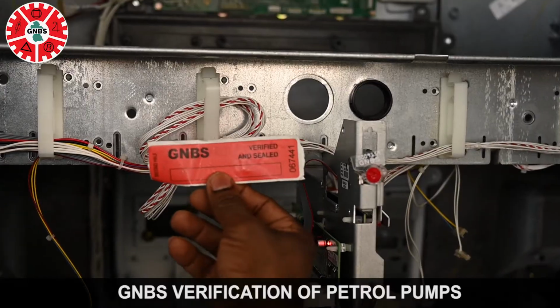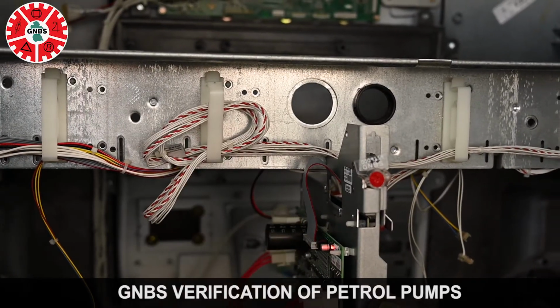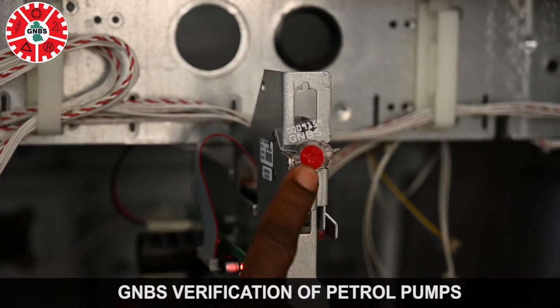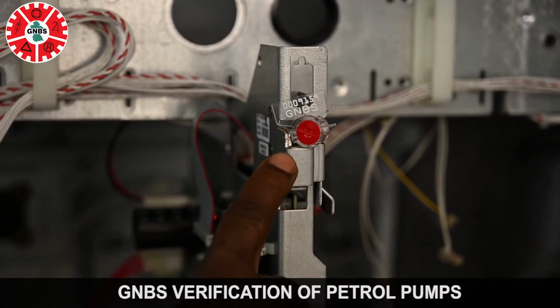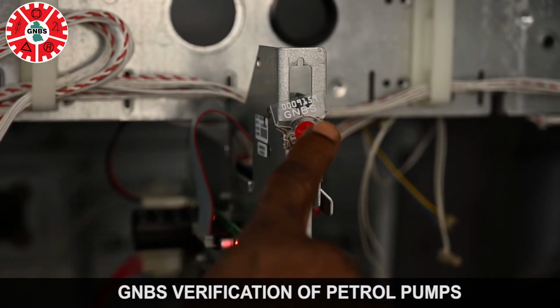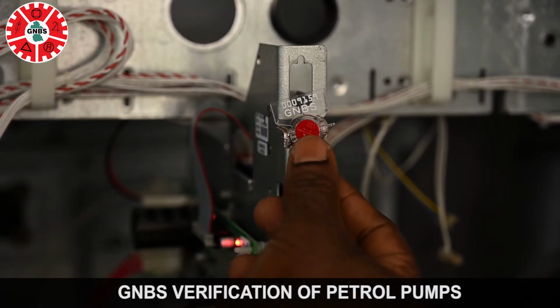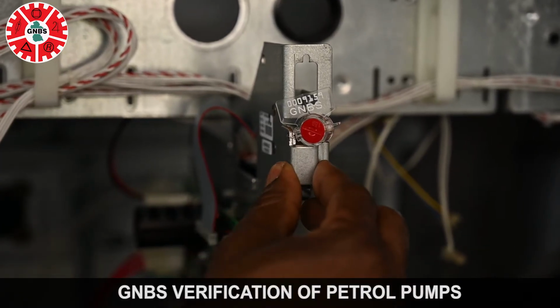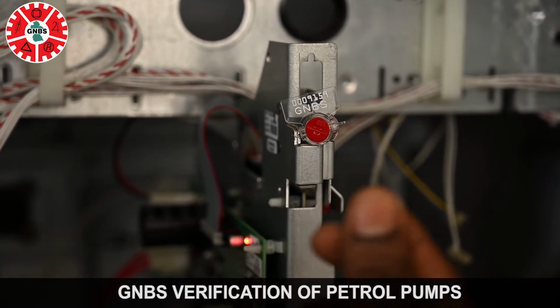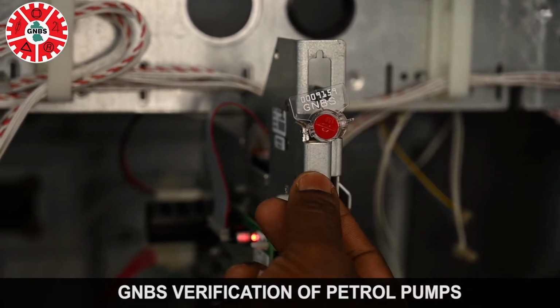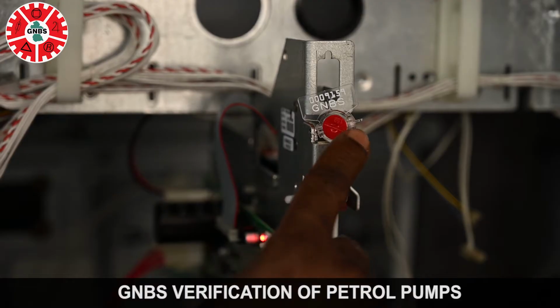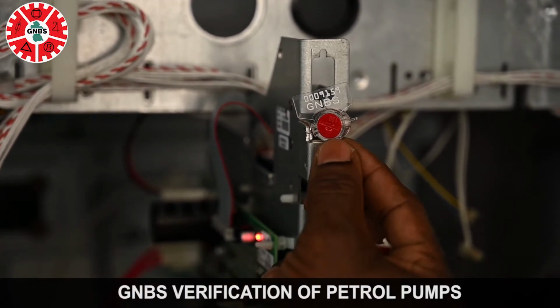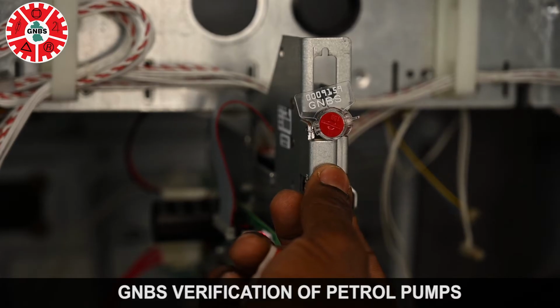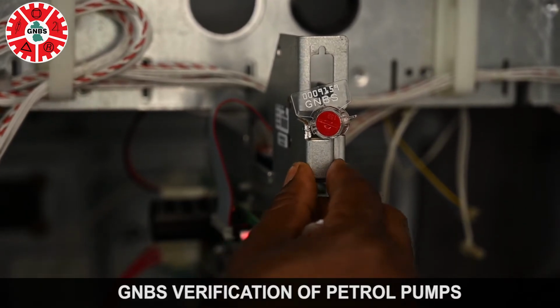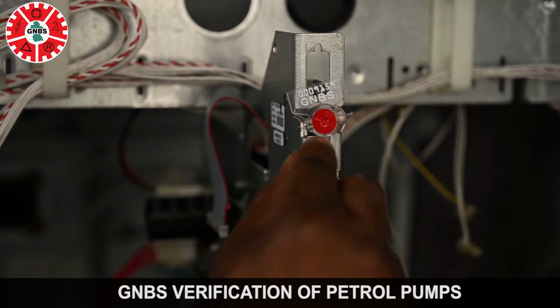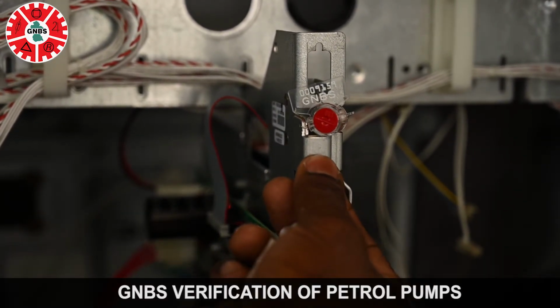In addition to the approval seal that I'm holding in my hand, there is also the security seal. Now this seal actually carries GNBS that you can see. It carries a number that we track with our logbook, and the purpose of this seal is to seal off the calibration mechanism. So just in case the station owner or anybody wants to do any adjustment to this pump, they will have to remove this seal before any adjustment can be done. So this is a way in which the GNBS will track to ensure that the calibration is intact and was left the same way at the last calibration.